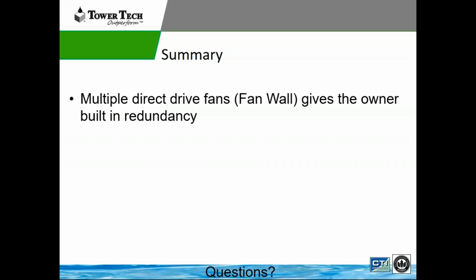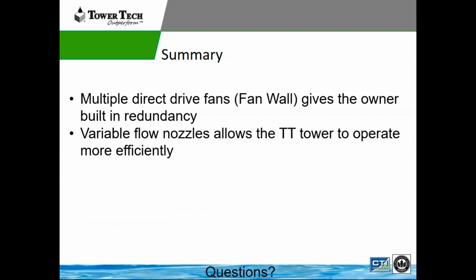So on a traditional tower system, if that fan fails, or something goes wrong with that fan system on a traditional tower, that's an emergency call. That's a crane, labor that has to fix it. On ours, we have a direct drive fan that's underneath. I have one guy that can, if he has the proper material, do a replacement of that motor system on his own. As we have the lockout, tagout, and the motor protection panel, we can operate all the other fans in the system and it's not an emergency phone call, which means I'm not paying overtime from a service side of it.